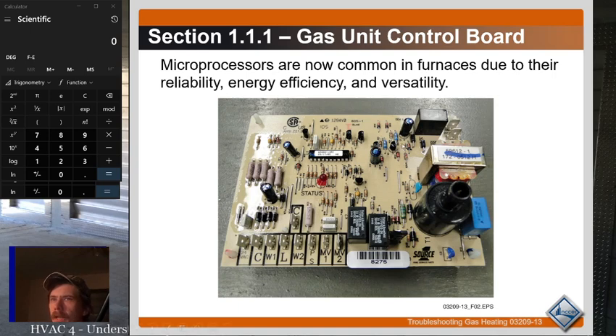Alright, and these things are almost universal. A circuit board that works on a hot surface igniter can work in almost any furnace that uses hot surface igniters, and a circuit board that does spark ignition can work in just about any furnace that uses spark ignition. The main difference between them is what wires go where. Okay, you could take a universal board and replace almost any hot surface ignition or spark ignition board in it. But of course, it's easier to use the one that came with the equipment. And if it's more complicated than the basic sequence of operation, obviously you'll need that particular board. But they all operate very, very close to the same.